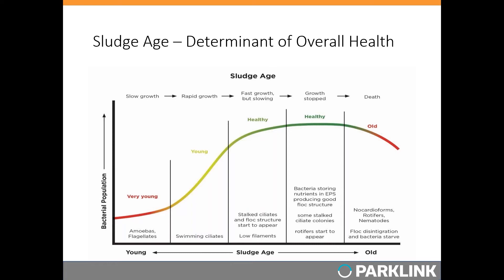If your sludge age stays too old for a prolonged period, you may get foam formation from fine particles and dead microbes floating on the surface, which stabilize air bubbles. Old sludge also favors the growth of Nocardia — branching filaments that look like little tumbleweeds under the microscope — which float on the surface and can cause large foaming events that upset your entire operation. Foam and scum also reduce oxygen diffusion into the water, leading to lower nitrification efficiency.